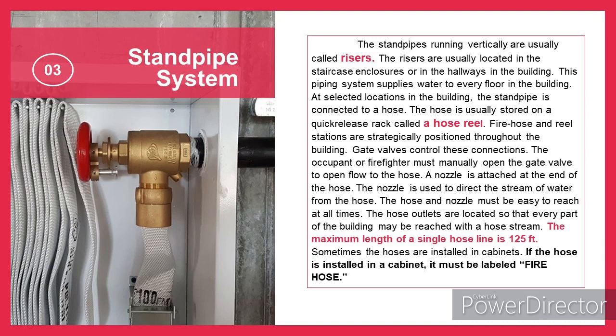At selected locations in the building, the standpipe is connected to a hose. The hose is usually stored on a quick-release rack called a hose reel. Fire hose and reel stations are strategically positioned throughout the building. Gate valves control these connections. The occupant or firefighter must manually open the gate valve to open flow to the hose. A nozzle is attached at the end of the hose. The nozzle is used to direct the stream of water from the hose.